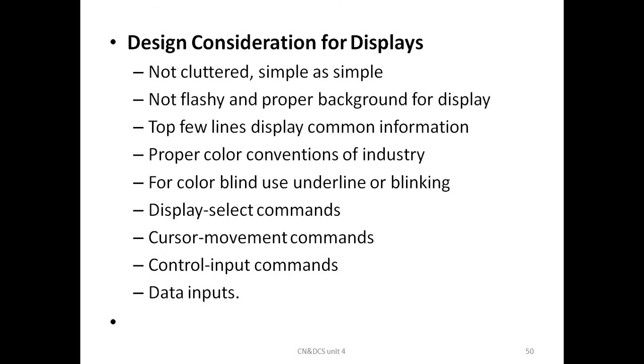Design considerations of display: not cluttered, simple, not flashy, and a proper background for display. Top few lines display common information. Proper color conventions of industry. For color blind, use underline or blinking. Display select commands, then cursor movement commands, then control input commands, then data inputs.